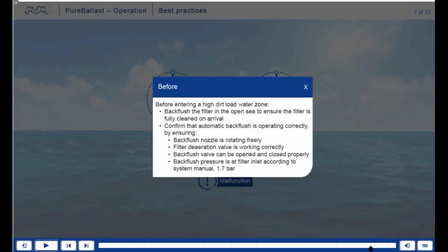Before entering a high dirt load water zone, backflush the filter in the open sea to ensure the filter is fully cleaned on arrival. Confirm that automatic backflush is operating correctly by ensuring the backflush nozzle is rotating freely, the filter deaeration valve is working correctly, and the backflush valve can be opened and closed properly. Backflush pressure at the filter inlet should be 1.7 bar according to the System Manual.